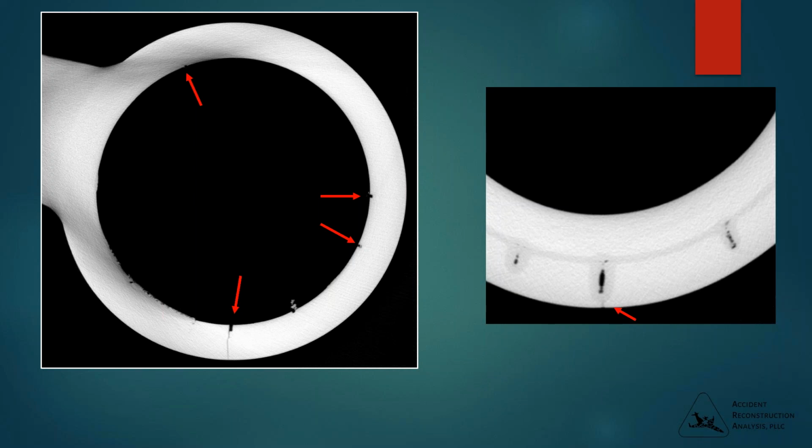And again, a higher magnification shot of the cross-sectional slice shown in the previous picture that shows, again, the crack penetrating the through wall, and you can see it faintly at the bottom of that image.